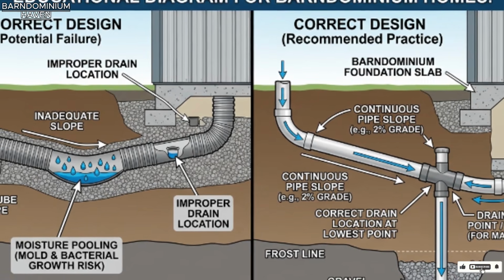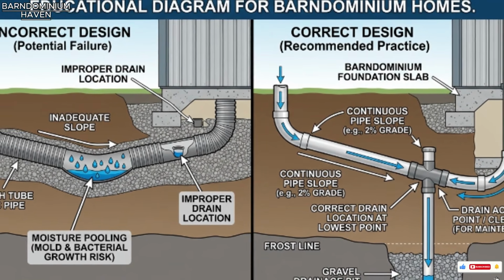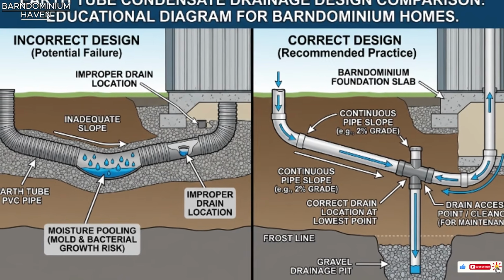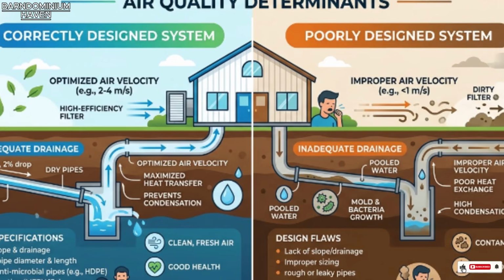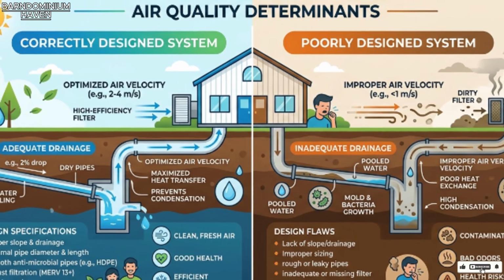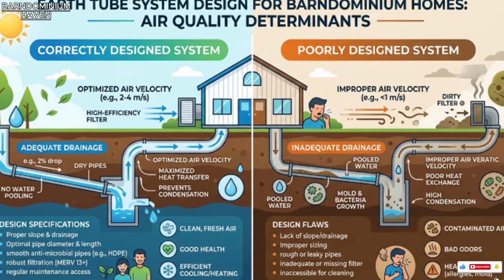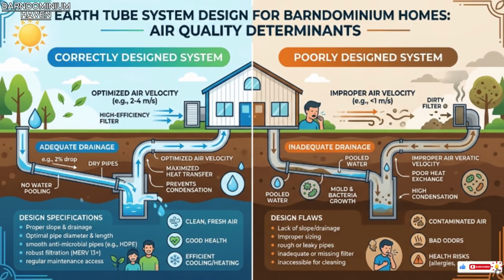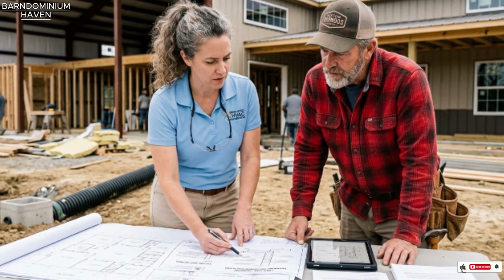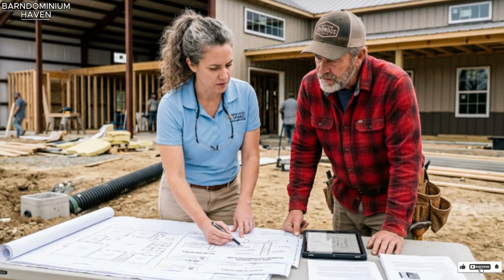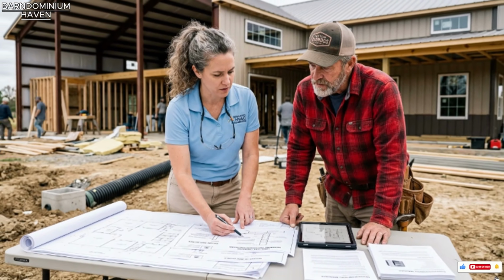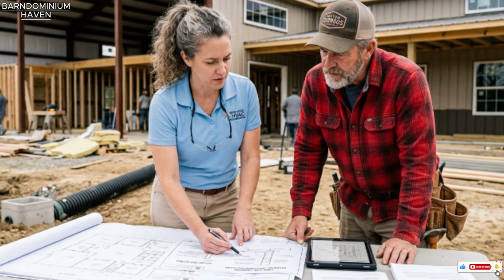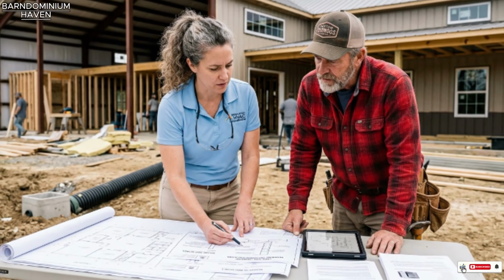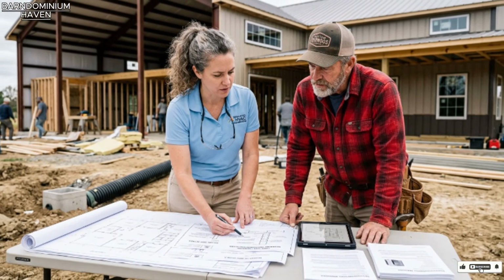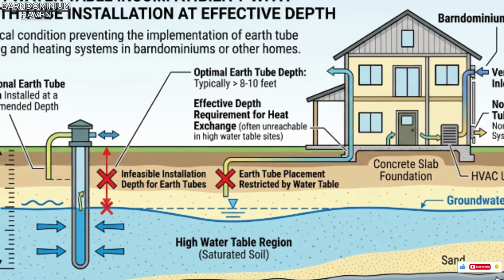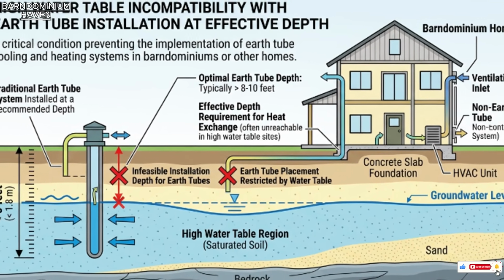A poorly designed earth tube does not deliver cool air. It delivers cool air contaminated with biological material. A condition that is invisible to the occupant and potentially hazardous to their health. The design specification for the condensate drainage system, the pipe slope, the drain location, the drain access, must be addressed by a mechanical engineer with specific earth tube experience, not by a general HVAC contractor encountering the system for the first time. High water table sites are incompatible with earth tube installation.